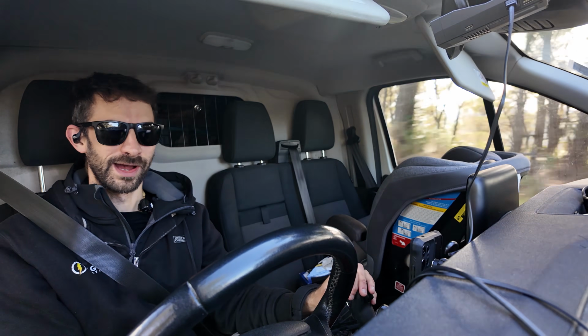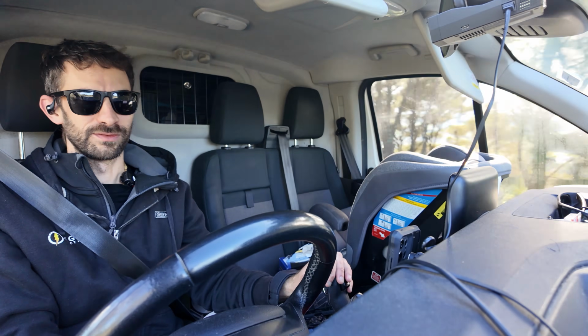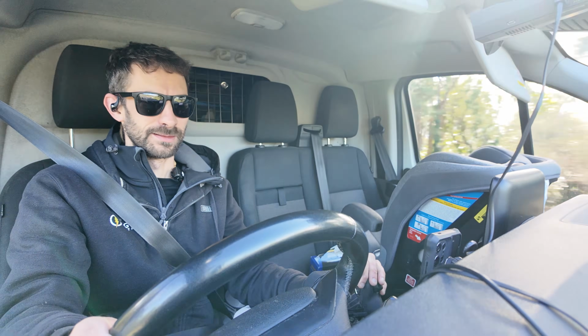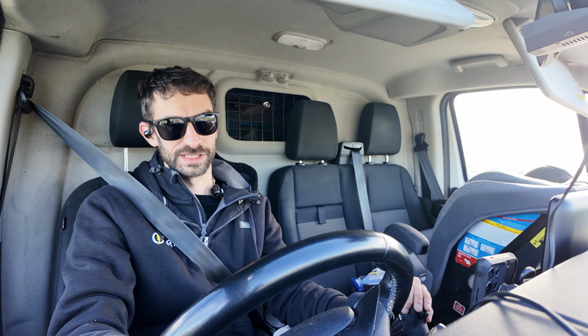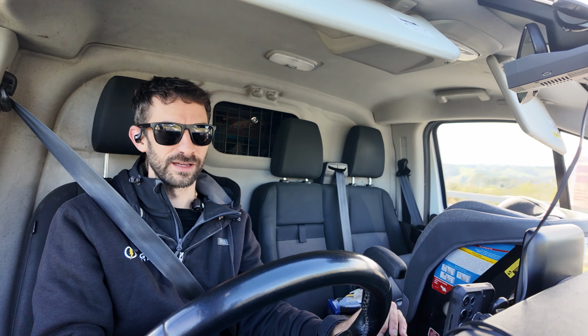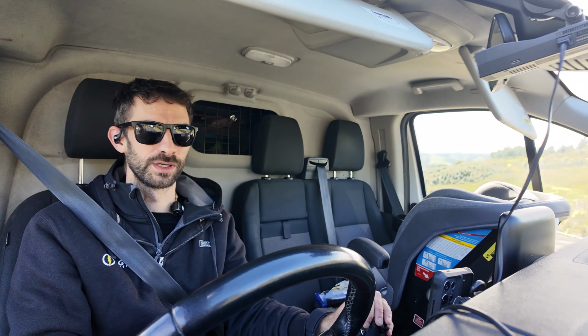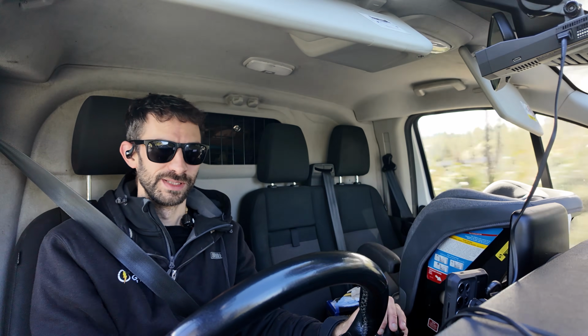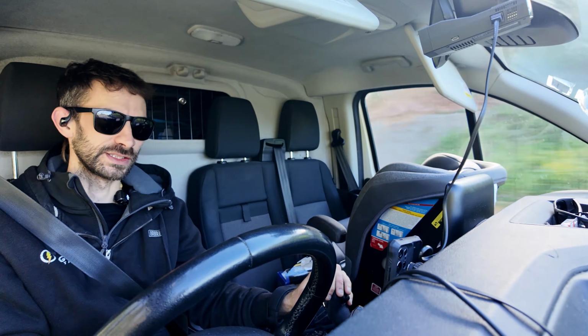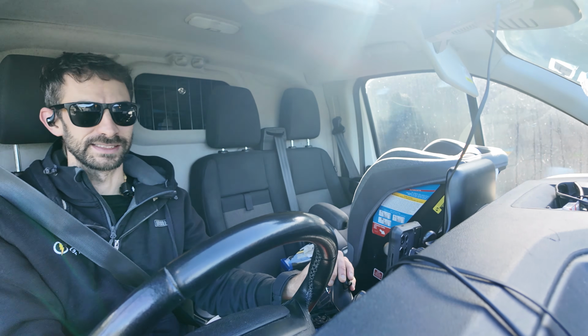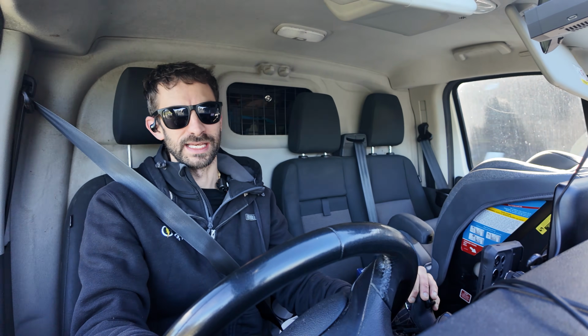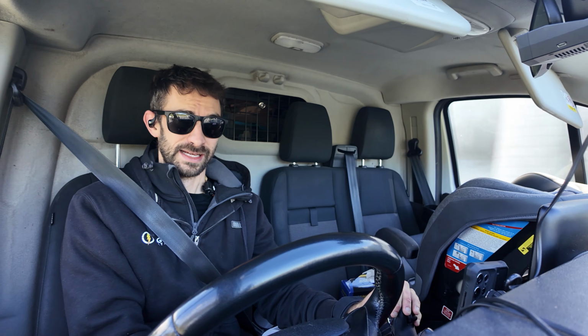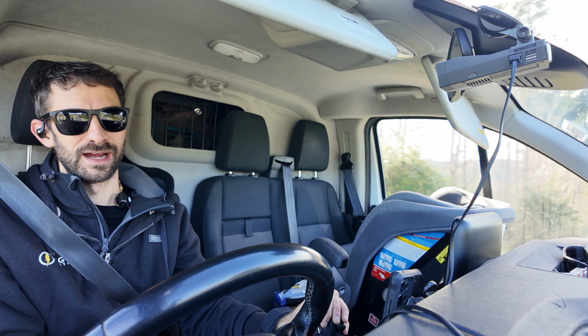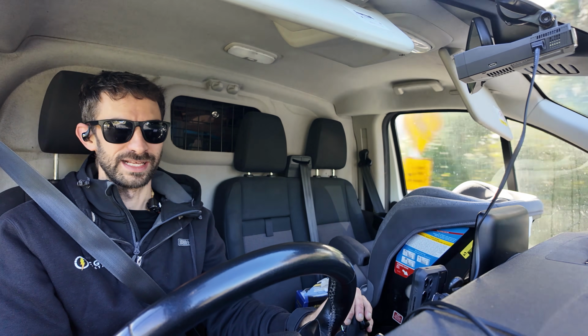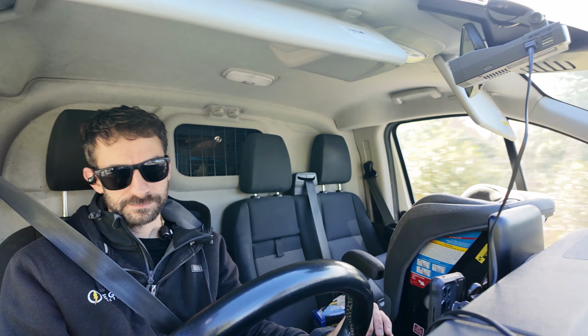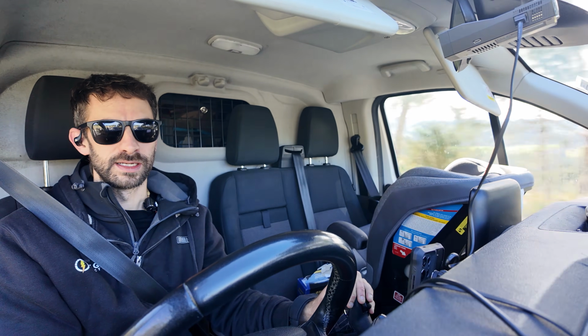You don't have to earth an appliance that doesn't have the same kind of risk of building up voltages as a whole transformer does. But that's why the traditional, old school way of personal protection is an isolation transformer. You've probably seen them, those big orange things, big heavy box, you plug it in. They used to be used on construction sites, but now we have RCDs. Nobody uses that anymore, both because RCDs are a lot safer than that, and also because those things are bulky and heavy and awkward. But they were considered to offer a decent amount of protection.